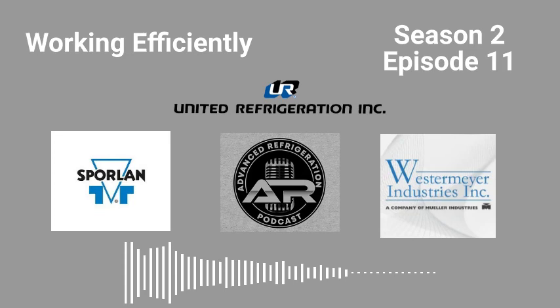Now what you could do is assign a Fieldpiece transducer, a Sporlan transducer, a Testo transducer - you could assign any of those transducers to that pressure for that evaporator, and then assign different temp sensors. Whether you have 2 Fieldpiece ones and 2 Testo ones, you could use all 4 - intermix tools together to get your readings. So now you're able to do 4 superheats at once, okay?